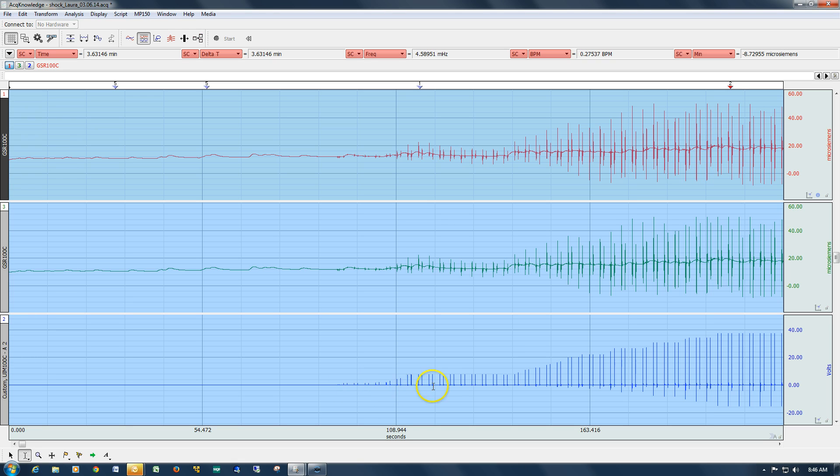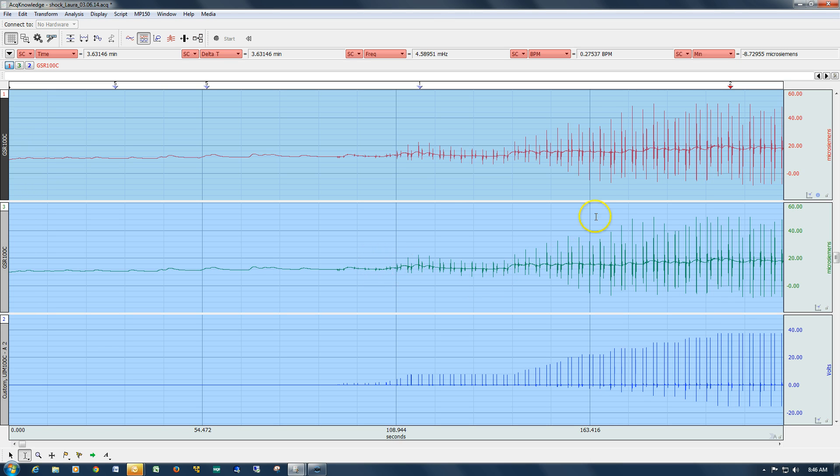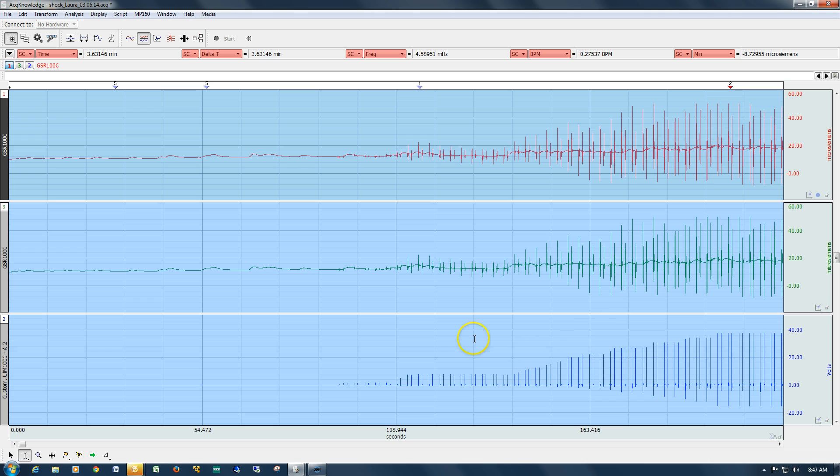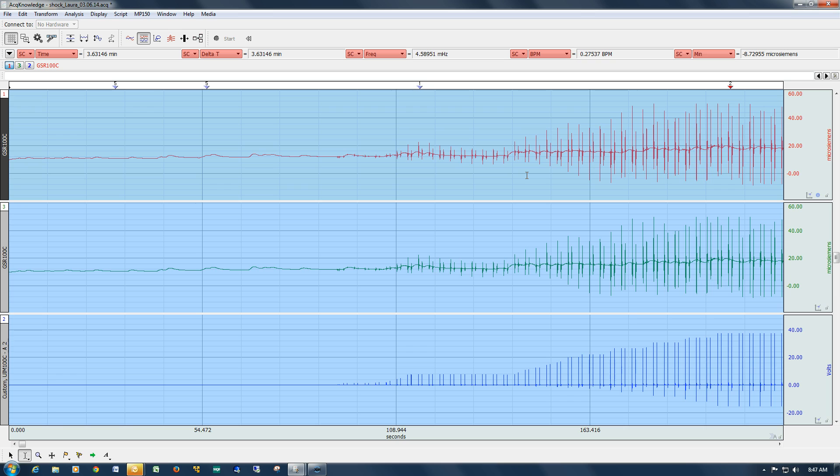The stimulator was firing pairs of electrical stimuli at a subject, and the subject had electrodes on for electrodermal activity, and the amplifier was picking up the electrical signal as it was being delivered to them from the stimulator. This happens quite often, and you need a convenient way of removing this signal contamination without actually distorting the waveform.